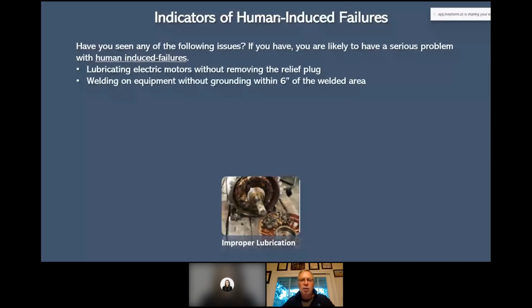Welding in equipment without grounding within 6 inches of the welded area. Oh my gosh. I was at a plant about a month ago, maybe 2 months. The vice president was there because they had a lot of problems with this plant. He said, man, we've got bearings failing, electrical problems, electronic problems. I don't know what all's going on. I said, well, it looks like you're adding a lot of new equipment, right? He said, yeah, we're adding new equipment everywhere.